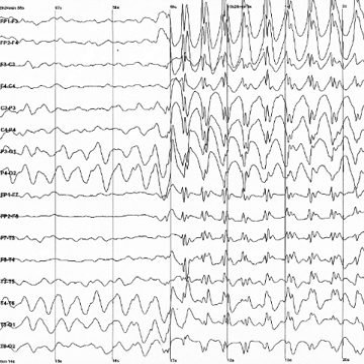Dry electrode signals depend upon mechanical contact. Therefore, it can be difficult getting a usable signal because of impedance between the skin and the electrode. Some EEG systems attempt to circumvent this issue by applying a saline solution. Others have a semi-dry nature and release small amounts of gel upon contact with the scalp. Another solution uses spring-loaded pin setups. These may be uncomfortable. They may also be dangerous if used in a situation where a patient could bump their head, since they could become lodged after an impact trauma incident. ARL also developed a visualization tool, Customizable Lighting Interface for the Visualization of EEGs (CLIVE), which showed how well two brains are synchronized.